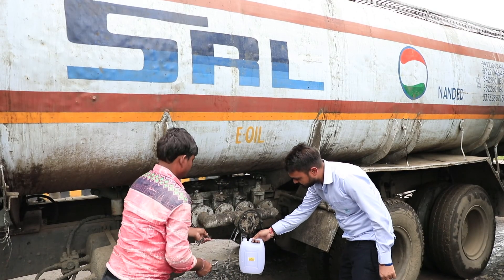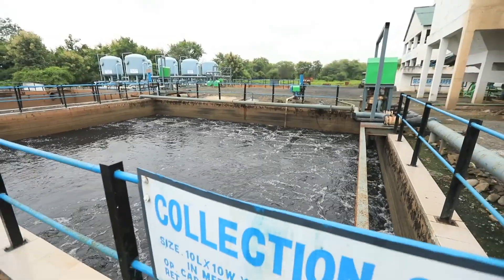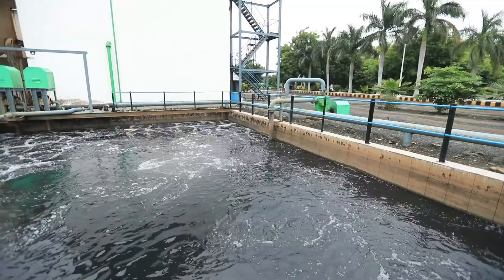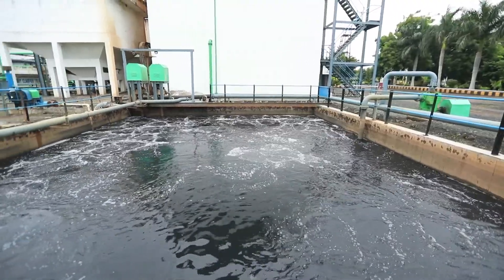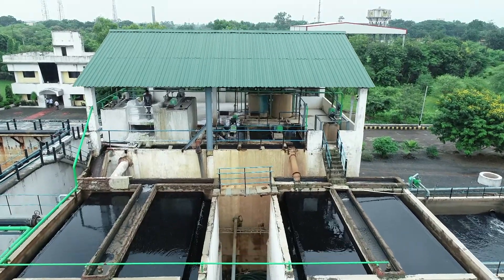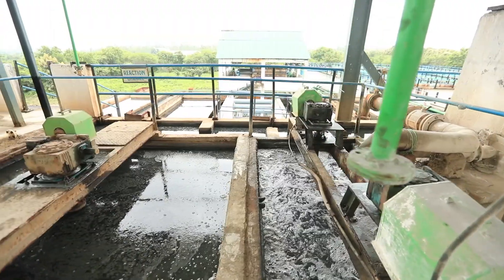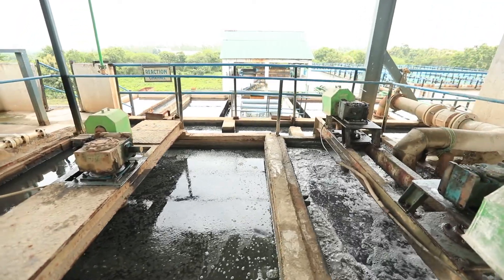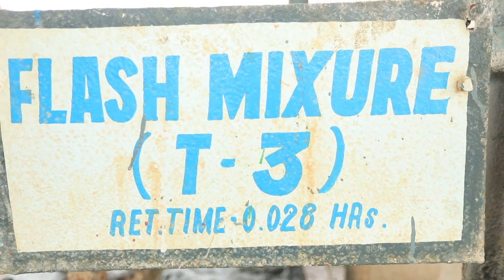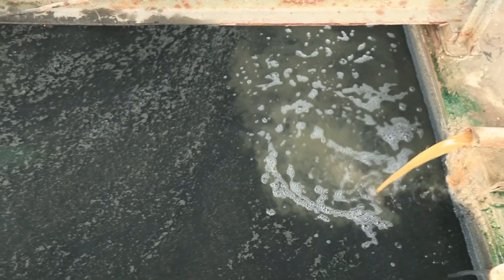Sampling is done to assess the quality of wastewater on set parameters, and effluent is then offloaded. Effluents collected in the collection sump are pumped to a screen and grit chamber to remove large objects, grit, and sand. The effluent is then routed to an equalization chamber, where through a physical process, the flow of wastewater is equalized along with its characteristics. Wastewater then flows to a flash mixer for addition and reaction of chemicals, and goes to a flocculator where impurities get coagulated.